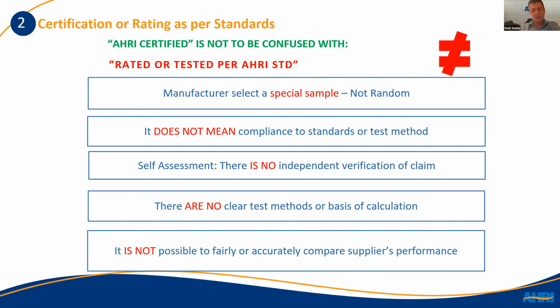So as you can see, rated per AHRI does not even mean tested per AHRI. It only means that this is what the manufacturer's own published data states the performance to be, for example at 35 degrees C. It's hard to know how manufacturers reach this value, and thus how to compare and how the product is selected. As for tested per AHRI, it all depends on the lab where it was tested. So in these cases, it's not possible to fairly and accurately compare products being evaluated by the owner.